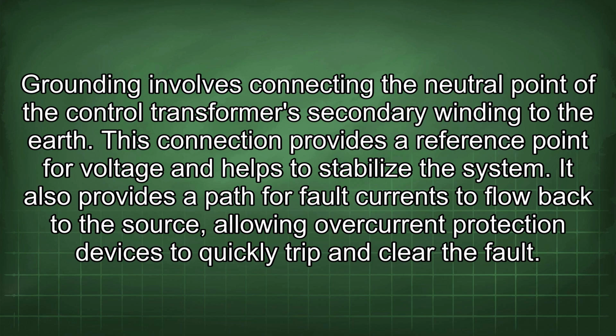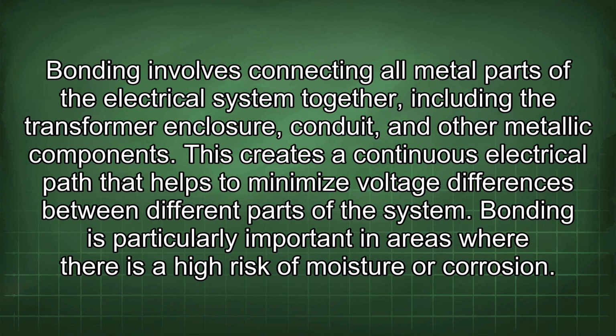Grounding involves connecting the neutral point of the control transformer's secondary winding to the earth. This connection provides a reference point for voltage and helps to stabilize the system. It also provides a path for fault currents to flow back to the source, allowing overcurrent protection devices to quickly trip and clear the fault. Bonding involves connecting all metal parts of the electrical system together, including the transformer enclosure, conduit, and other metallic components. This creates a continuous electrical path that helps to minimize voltage differences between different parts of the system. Bonding is particularly important in areas where there is a high risk of moisture or corrosion.